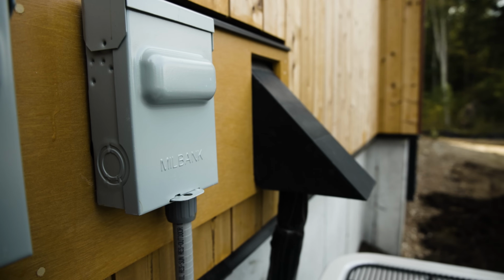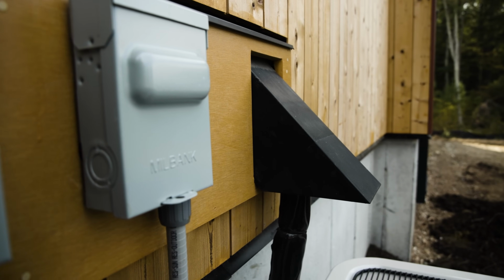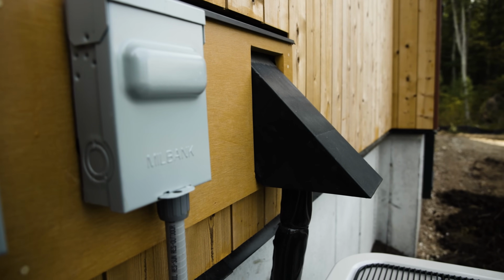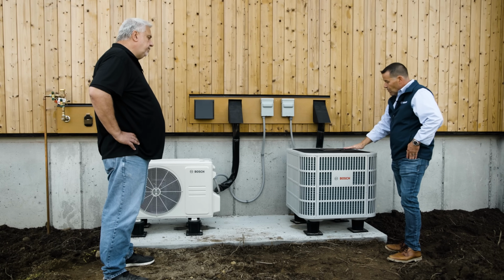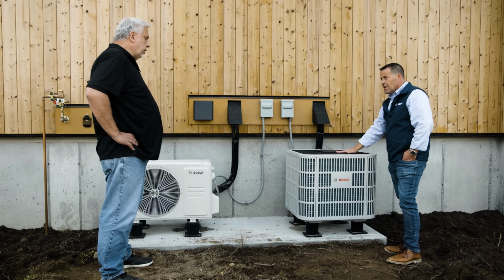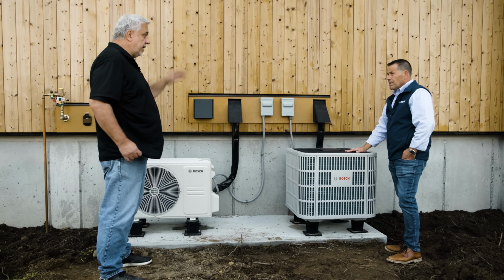It knows one thing: it wants to keep that coil at 47 degrees no matter what's going on outside or inside. So this unit ranges all the way from 36% capacity, creating its own variation to satisfy that need.